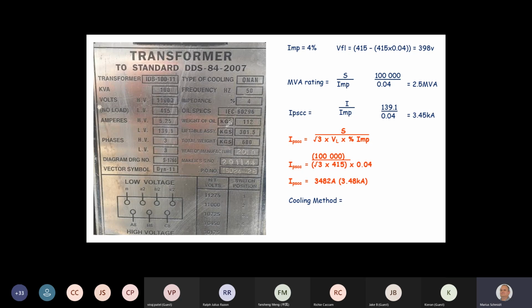Right, Jesse. Right, so Clayton, just to answer your question again, answer the question they want. Do they want your short circuit current in amps or in kiloamps? Secondly, do they want the fault level in million volt amps, MVA, or in kVA? But normally, your fault level will be in MVA, and your short circuit current will be in kiloamps. That is the normal terms in which they answer it.